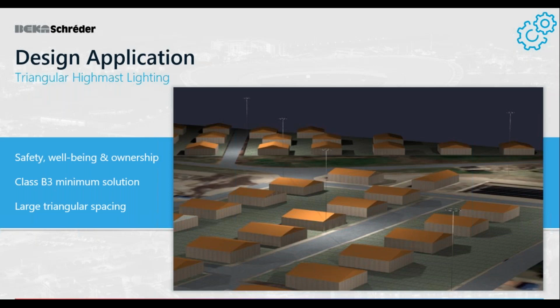from 10 till about 12 at night to 70% of its initial luminous flux. From 12 or 2400 until 0400, we can reduce it further, the flux from 70% to 30%, and then again from 0400 to 0600, we ramp it back up to 100%, getting ready for the morning traffic expected, for the people going to work. And all of those dimming profiles have compounded in energy savings, and over a year that is an immense saving of electricity, which further assists in reducing the load on our constrained energy utility. And this also is something that can be controlled by the stadium controller that Mr. Donnie van der Nest will later discuss.